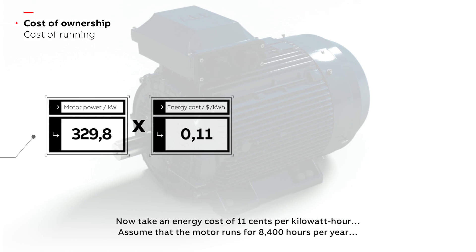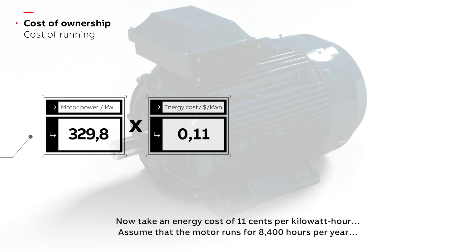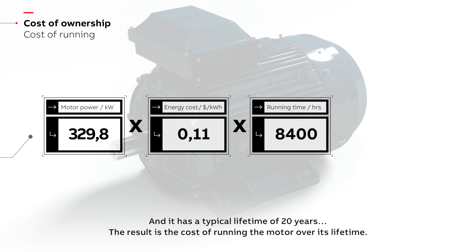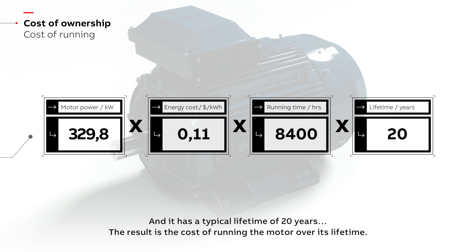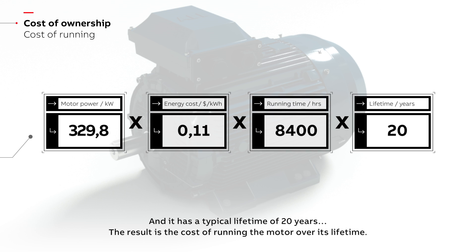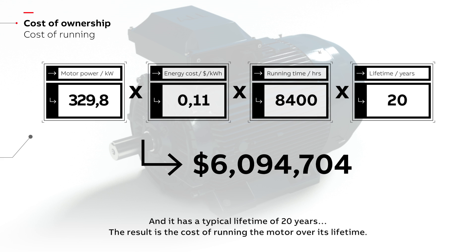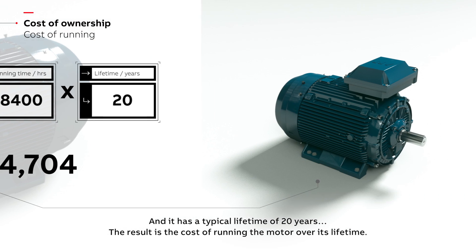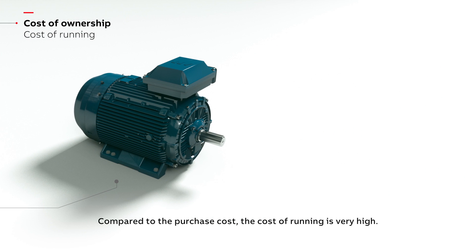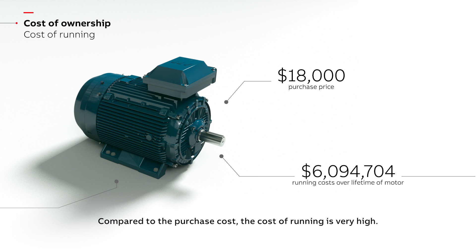Now take an energy cost of 11 cents per kilowatt hour. Assume that the motor runs for 8,400 hours per year and it has a typical lifetime of 20 years. The result is the cost of running the motor over its lifetime. Compared to the purchase cost, the cost of running is very high.